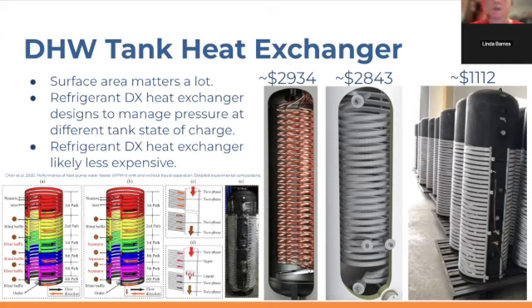So hence why there's a fairly significant price difference between the indirect fire internal heat exchanger domestic hot water tanks and the tanks that receive refrigerant, where the heat from the refrigerant directly exchanges through the tank wall into the water inside the tank. Now, this type of heat exchanger, the wraparound tank heat exchanger, has only in recent years become a viable option.